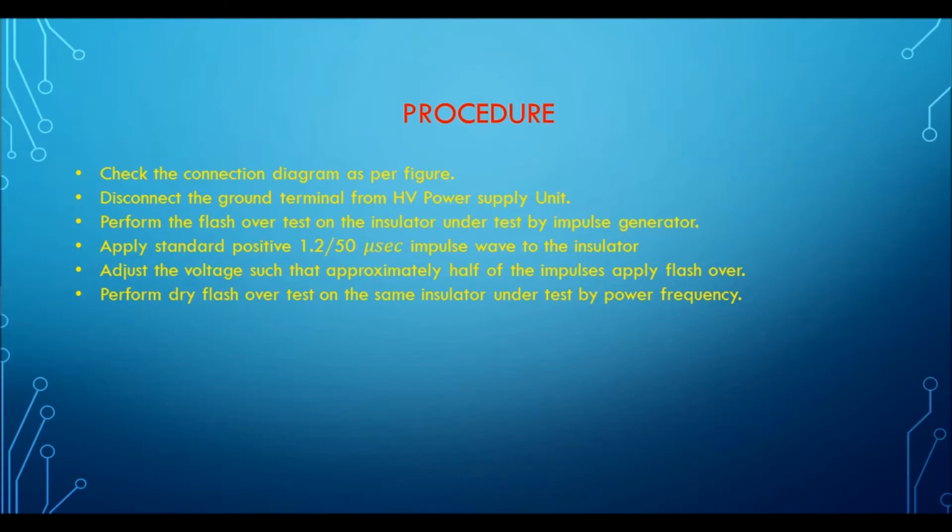First apply the impulse flashover voltage to an insulator. Then take the reading. Then the same insulator is connected to the AC power frequency voltage. Then apply AC power frequency voltage and note down the flashover voltage at AC power frequency. These are the procedures.